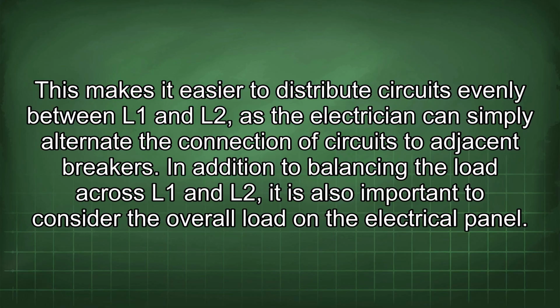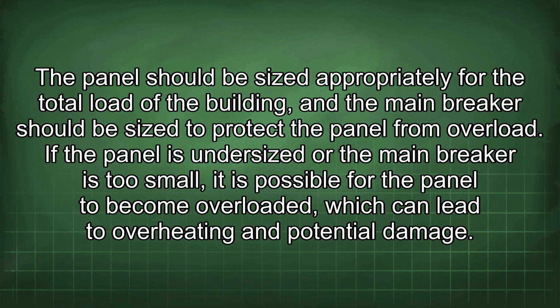In addition to balancing the load across L1 and L2, it is also important to consider the overall load on the electrical panel. The panel should be sized appropriately for the total load of the building, and the main breaker should be sized to protect the panel from overload. If the panel is undersized or the main breaker is too small, it is possible for the panel to become overloaded, which can lead to overheating and potential damage.